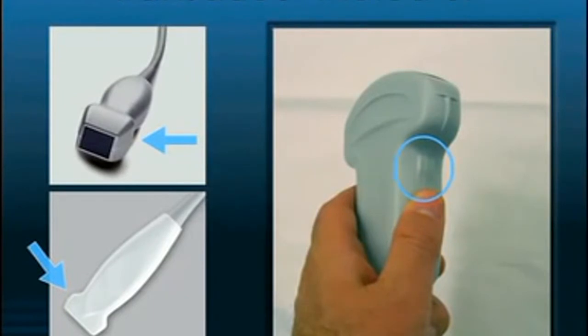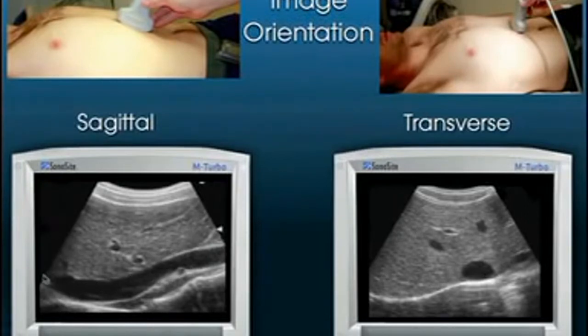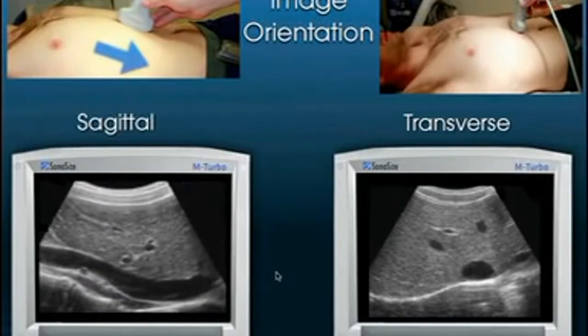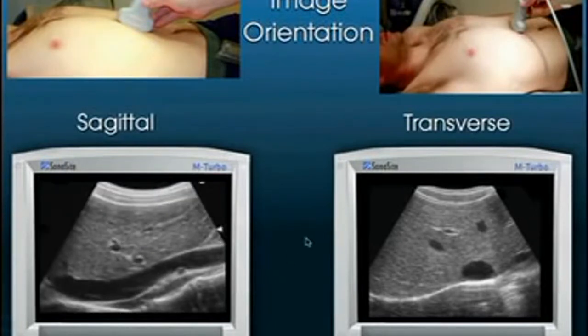Each transducer has an indicator, and the indicator follows a standard convention: towards the patient's head in a sagittal view, and towards the patient's right in a transverse view. Looking at the inferior vena cava in a sagittal view, the indicator towards the head means the top of the screen is towards the head and the bottom towards the feet. If you accidentally aim the indicator towards the feet, the IVC appears upside down — still interpretable, but against the convention in the United States.